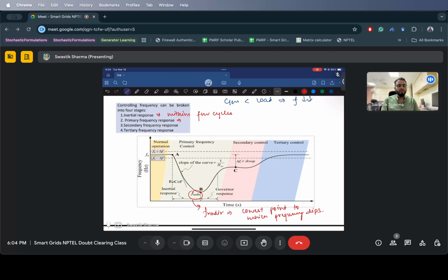In primary frequency control, first of all, it is also automatic. Even though it is automatic, it does not act immediately like the inertial response. It takes time. Control algorithms take some finite amount of time, right? So next comes primary frequency control, in which you control the governor or your droop control. So governor or droop control falls into this.